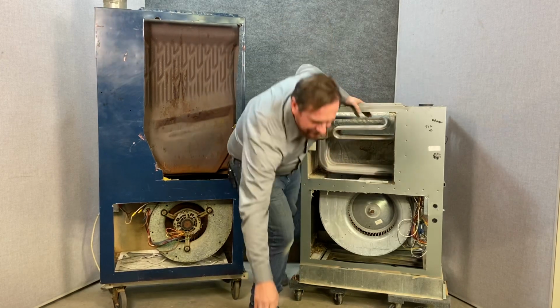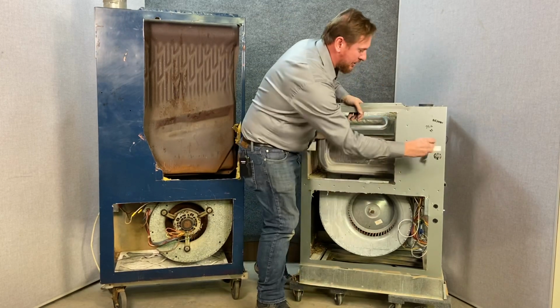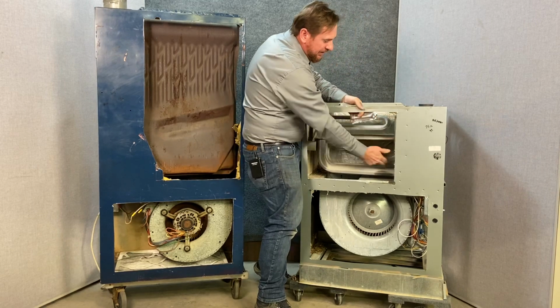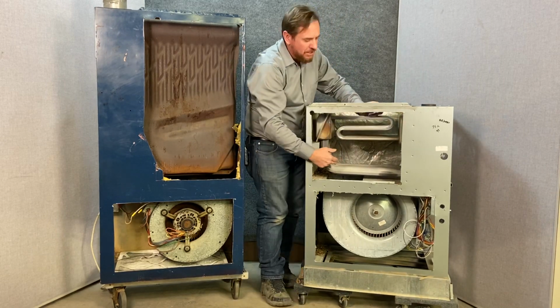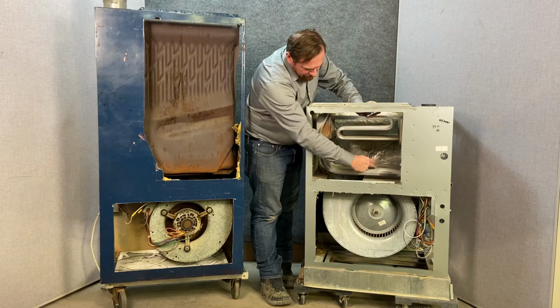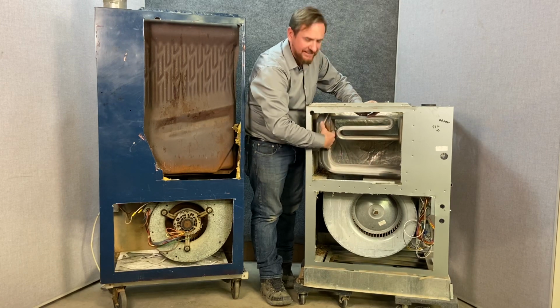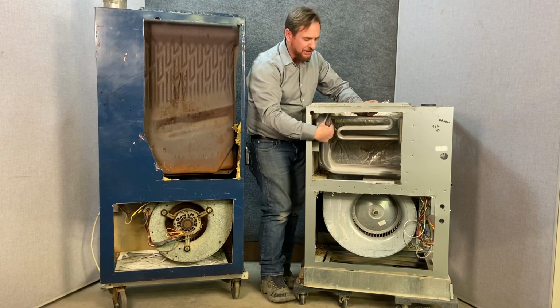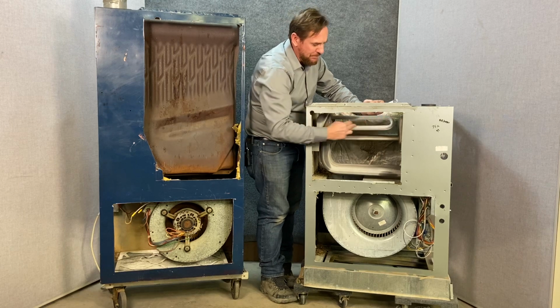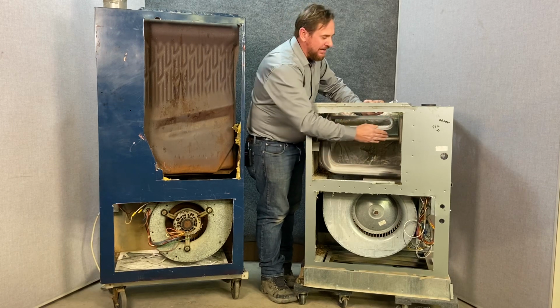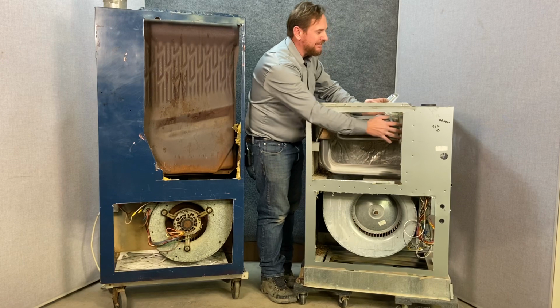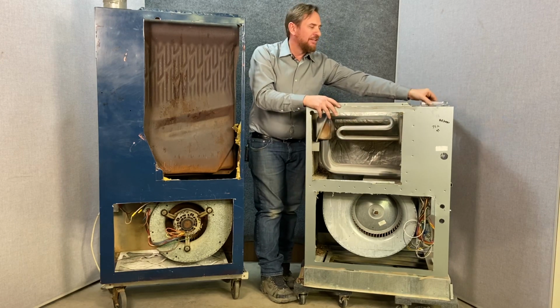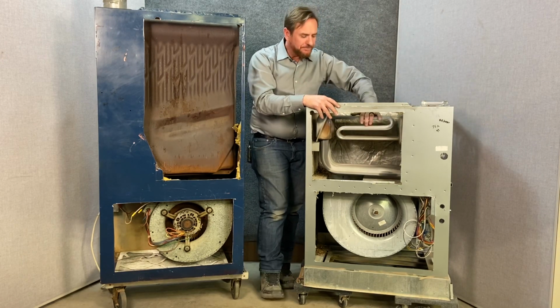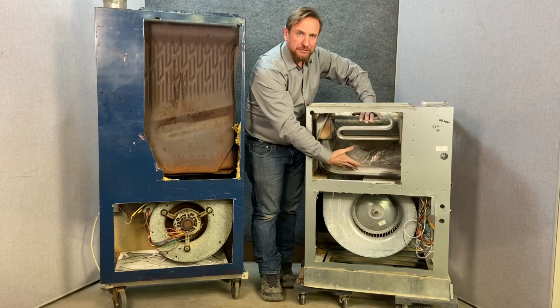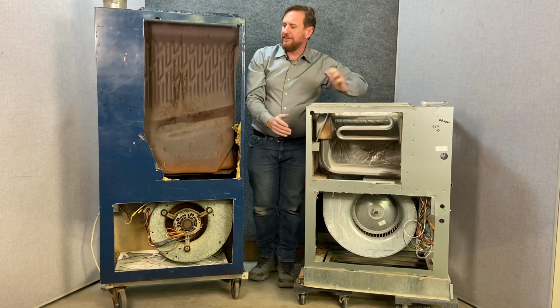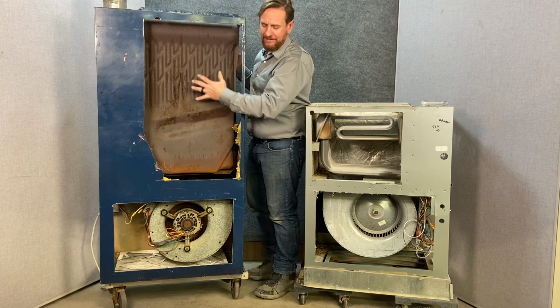These little burners are on the other side, and it actually shoots the flame inside of this heat exchanger. The flame burns no more than this far here, then it collects together. Those gases are still very warm, so the gases continue to run back and forth through the secondary tubing, and that collects in a box here that goes to our inducer fan that's pulling that draft out. So a whole lot smaller space, and we can transfer more heat versus this big long system here.